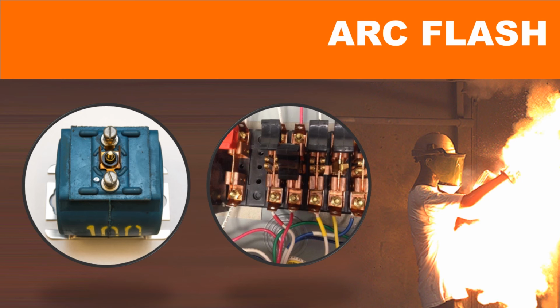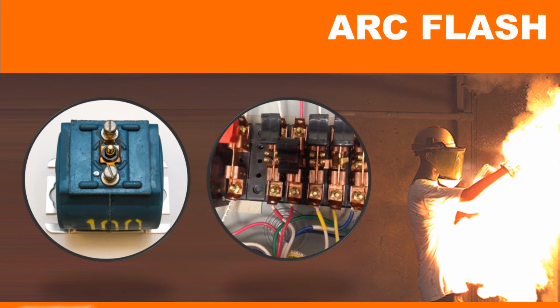Ordinarily, the current flows through the meter at a low resistance. But when you remove the meter, the low resistance is replaced by high resistance, which produces a high voltage arc flash. By engaging the shunt bar, the current flows directly through the CT, providing a low resistance path. Meter sites with test switches can be used to bypass current through the meter so it can be safely removed.